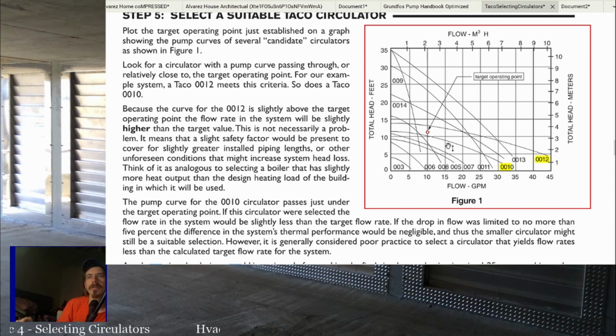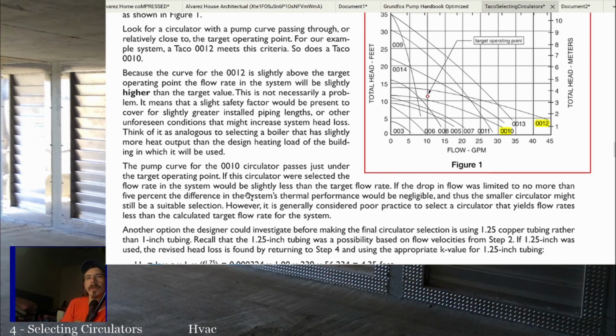The pump curve for a 0010 passes just under the target operating point. If the circulator were selected for the flow rate, the flow rate in the system would be slightly less than the target flow rate. If the drop in flow was limited to no more than 5% of the difference, the effect on the system's thermal performance would be negligible, and thus the smaller circulator might still be a suitable selection. So if you're going to go below it, you want to make sure that the loss is no more than 5%. That basically gives you another 5% of wiggle room for your plus or minus 10%. However, it's generally considered poor practice to select a circulator that yields flow rates less than the calculated target flow rate for the system.